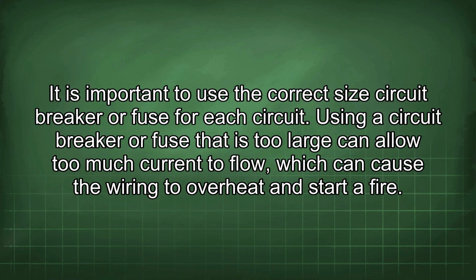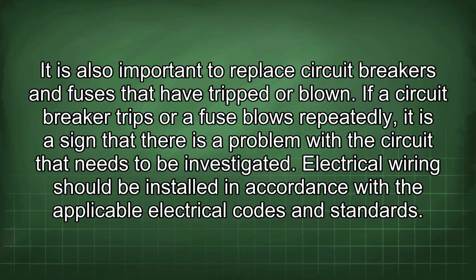It is important to use the correct size circuit breaker or fuse for each circuit. Using a circuit breaker or fuse that is too large can allow too much current to flow, which can cause the wiring to overheat and start a fire. It is also important to replace circuit breakers and fuses that have tripped or blown. If a circuit breaker trips or a fuse blows repeatedly, it is a sign that there is a problem with the circuit that needs to be investigated.